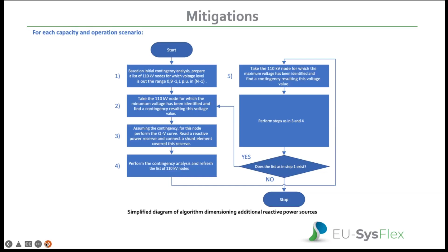The main algorithm of our study to dimension the additional reactive power sources is to identify the critical contingencies, and perform QV voltage stability analysis for those critical contingencies and nodes. We find the stability margin for those nodes, or what amount of reactive power is needed to keep the voltages and node stability at the specific level, and install a shunt element that will cover this reserve. We perform these steps in a loop until we no longer find any 110 kV node which, in those identified contingencies, does not meet the required voltage levels. So the next slide, please.